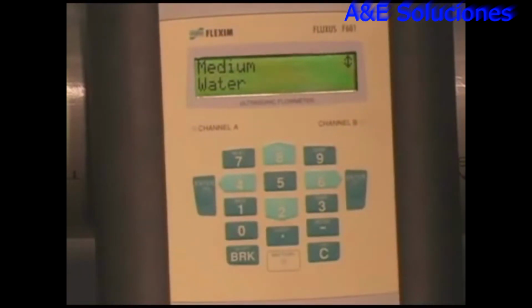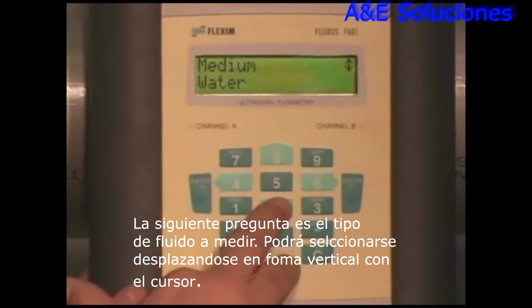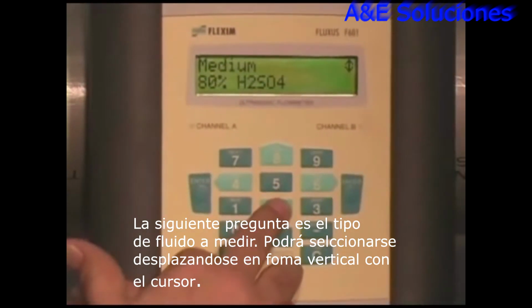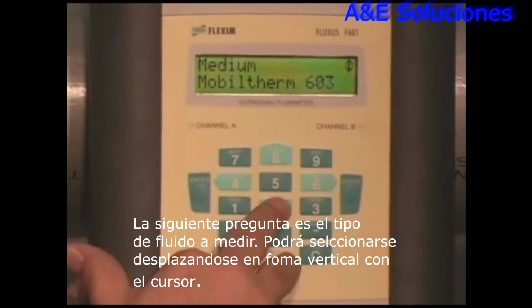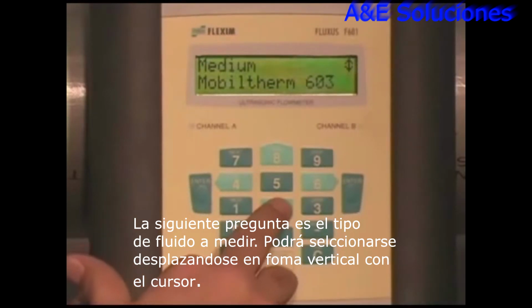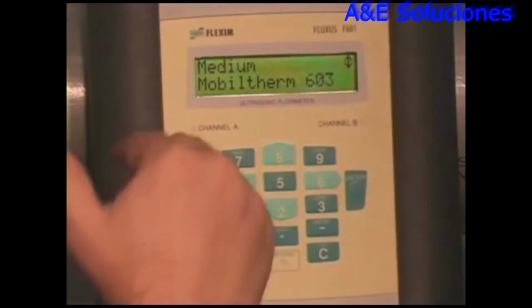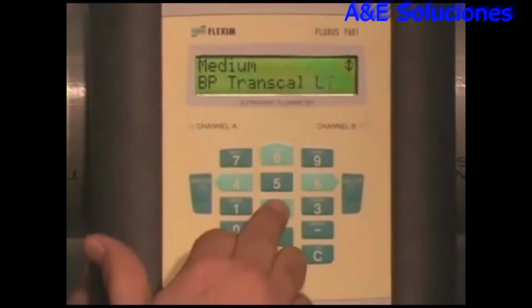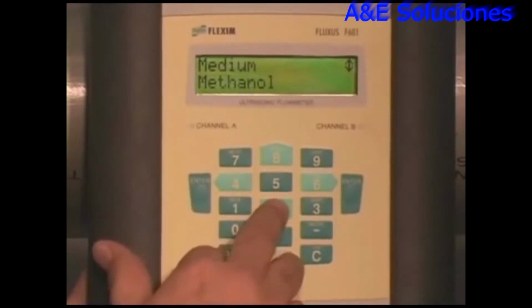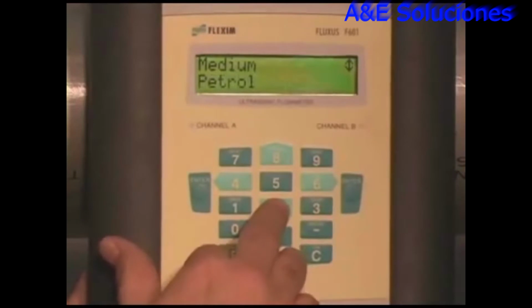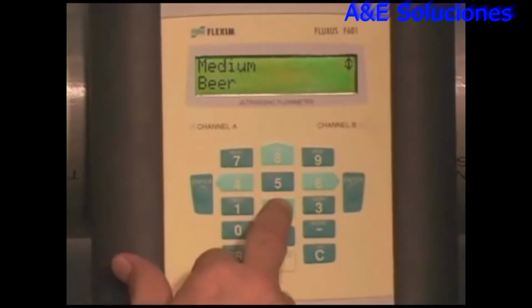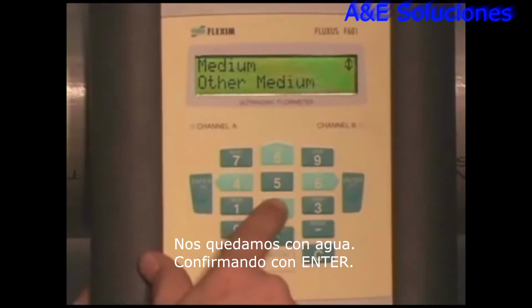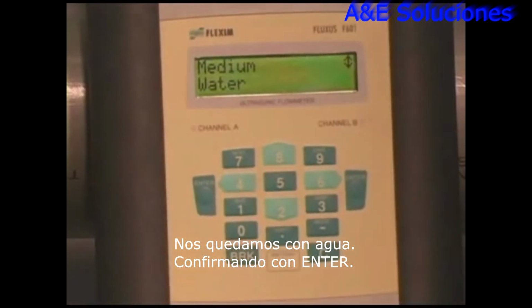Next question it asks is, what is your liquid medium? Here you'll see it's got water, and I'll just run real quick through a lot of the choices: hydrofluoric, caustic, glycol, certain glycol percents, which you'll see a lot in HVAC type applications. We have some Mobiltherms where you'll see in very high temperature applications where we tend to use our wave injector and go up to 700 degrees. And continue around, ethanol, methanol, until we find water again. Diesel, crude oil, juice, milk, beer, of course, because it's a German product, and other medium, and back to water. Okay, so now we got water.